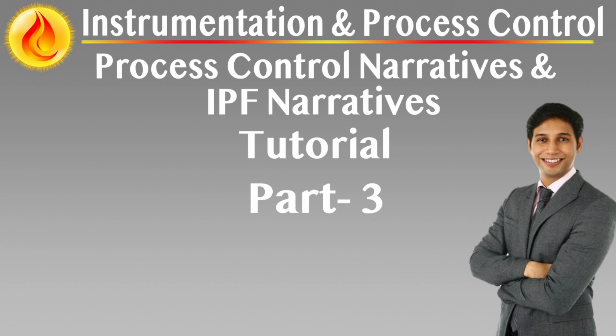They are used during design, verification, testing, and operational phases to ensure consistent understanding and implementation of instrumented protective functions, IPFs. CEDs serve as the bridge between process safety design and control system programming. They are used by engineers, system integrators, operators, and auditors to confirm that all protective actions are correctly linked, clearly defined, and appropriately grouped for implementation and review.